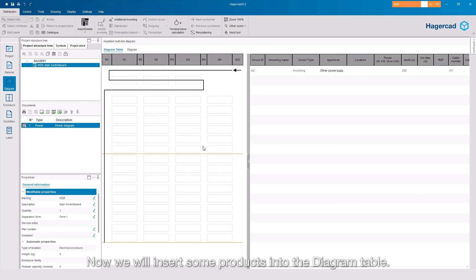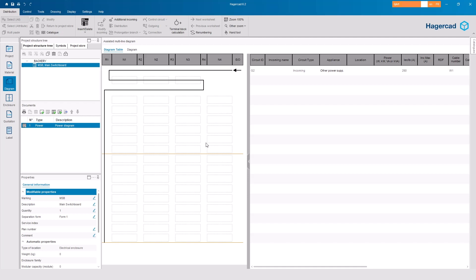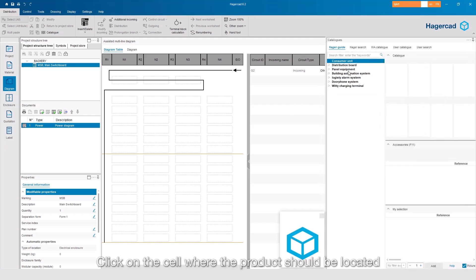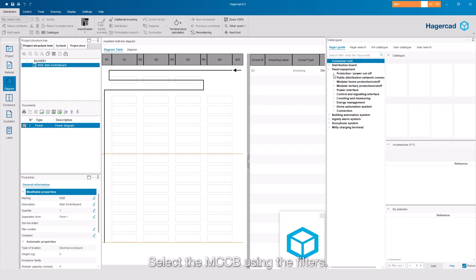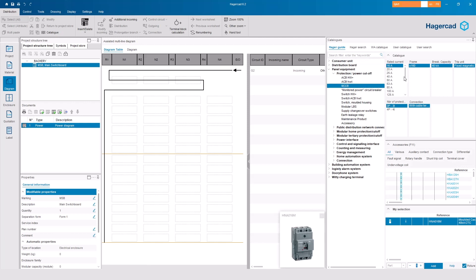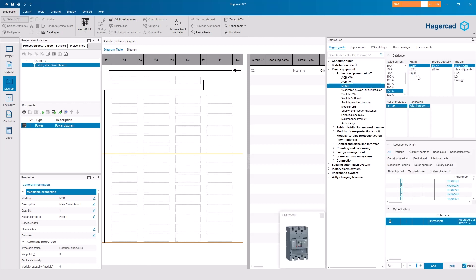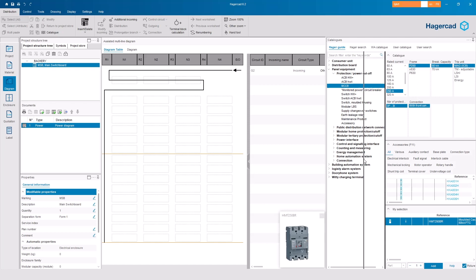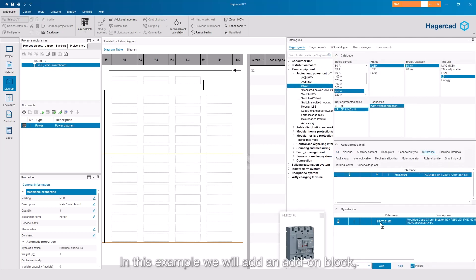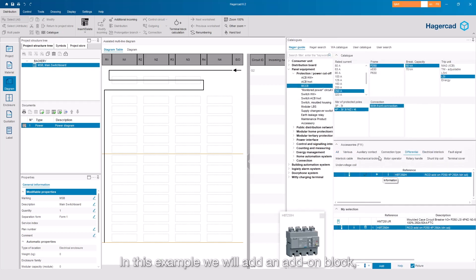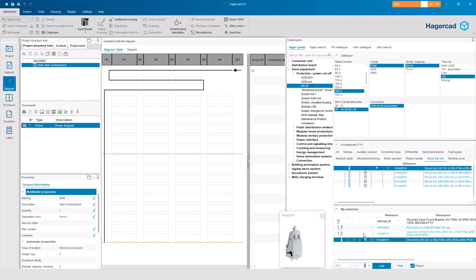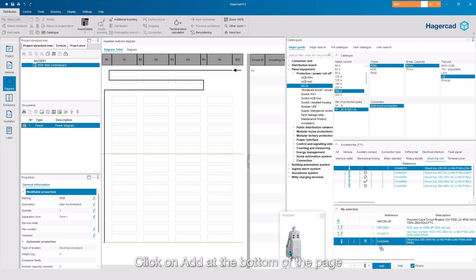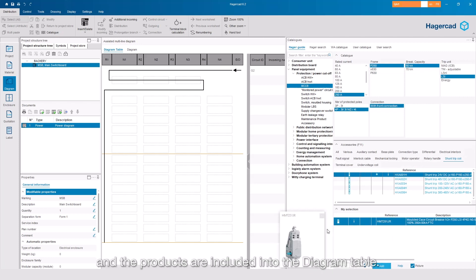Now we will insert some products into the Diagram table. Firstly, we have the main switchgear. Click on the cell where the product should be located and enter the catalogue. Select the MCCB using the filters. Add the accessories if needed. In this example, we will add an add-on block, an auxiliary contact, and a shunt trip. Click on Add at the bottom of the page and the products are included into the diagram table.